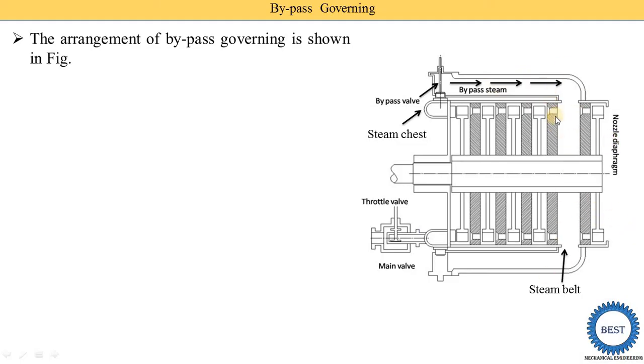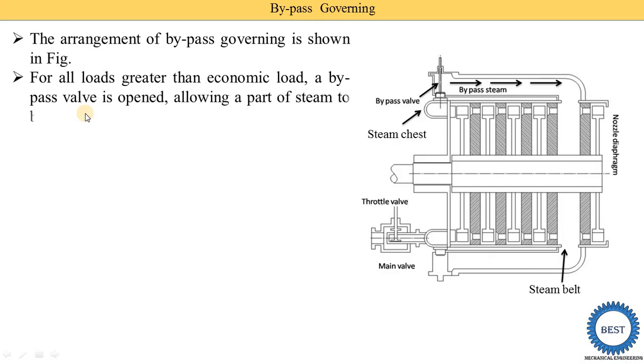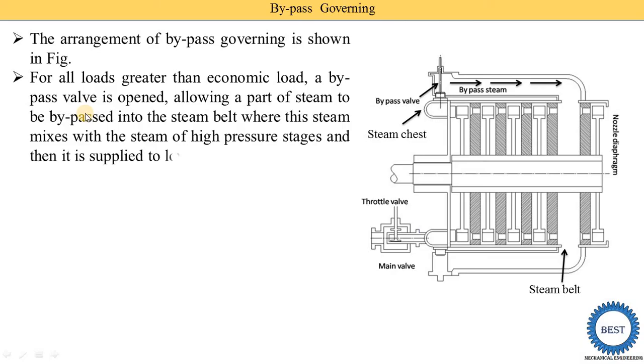The steam coming out from the high pressure stage is mixed with the bypass steam and then supplied to the low pressure stage. The place at which the bypass steam and the steam from the high pressure stage are mixed is called the steam belt, and this portion is called the steam chest. For all loads greater than the economic load — that is, more than 80 percent of turbine capacity — the bypass valve is open; otherwise, the bypass valve is closed.